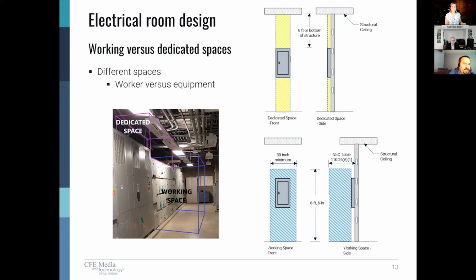So the code dictates that we have these spaces. The dedicated space is the space that is defined by the footprint of the gear up 6 feet or to the bottom of structure, whichever is lower. And the working space is the width of the equipment. And then NEC table 110.26(A)(1) defines the depth of that equipment. We'll get into that here in a little bit. That minimum working space width needs to be a minimum of 30 inches or the width of the equipment.